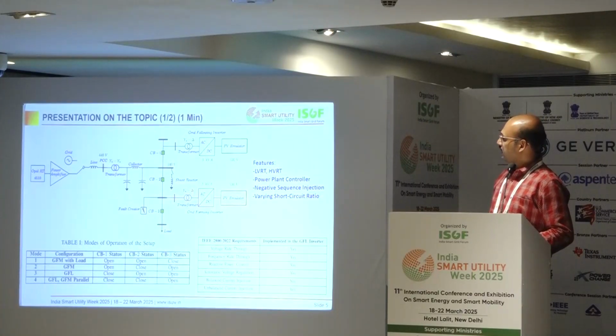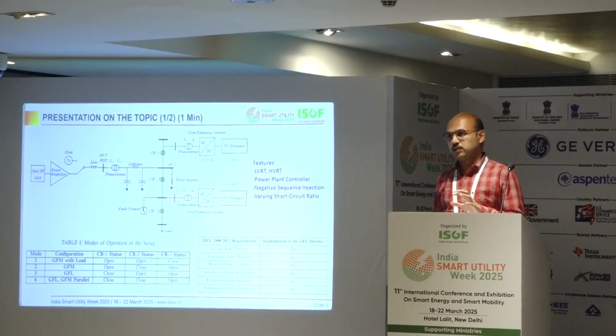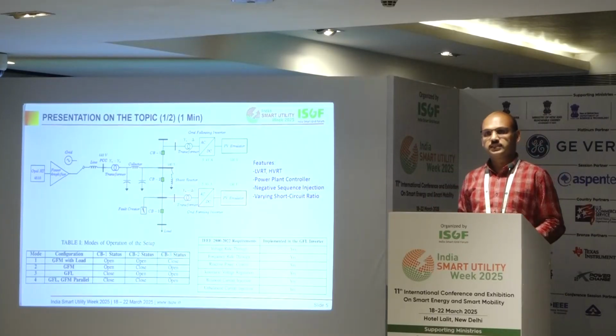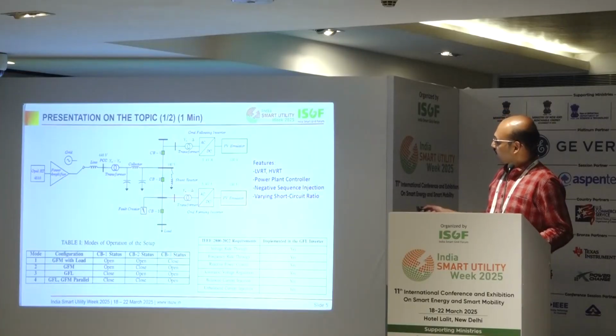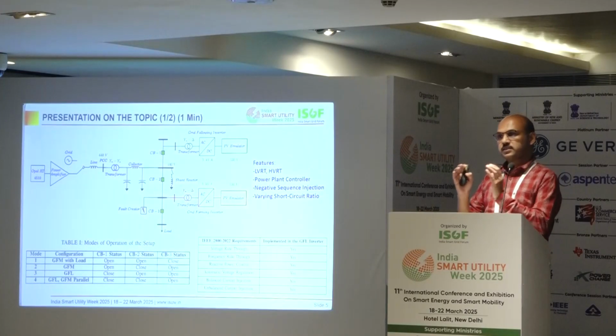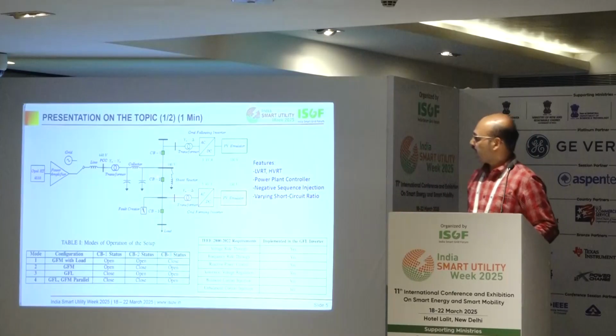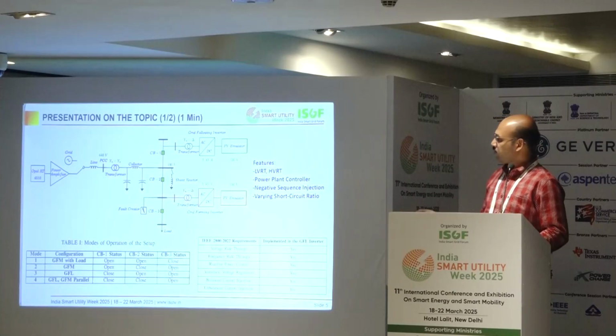Then each inverter has its own transformer. The output of this transformer goes to a 1.5 breaker scheme, where each breaker is a motorized breaker that can be controlled by digital signal. After this 1.5 breaker scheme, we represent the collector system of the plant through an LC equivalent representation of the whole collector system.